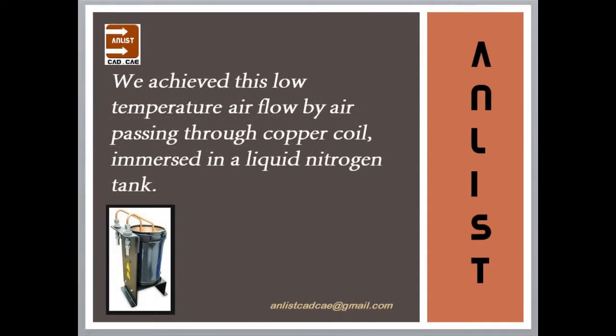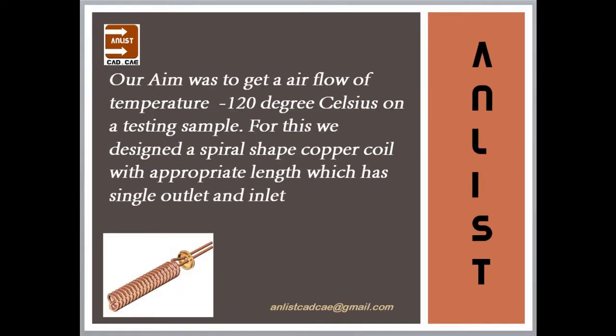We could achieve this low temperature by air passing through a copper coil immersed in liquid nitrogen. Our aim was to get an airflow temperature of minus 120 degrees Celsius on a testing sample. For this we designed a spiral shape copper coil with appropriate length, which has a single outlet and inlet.